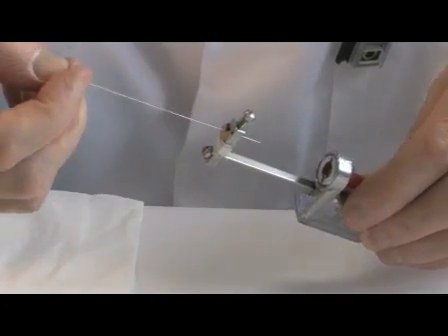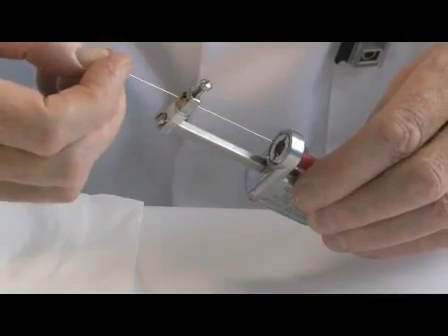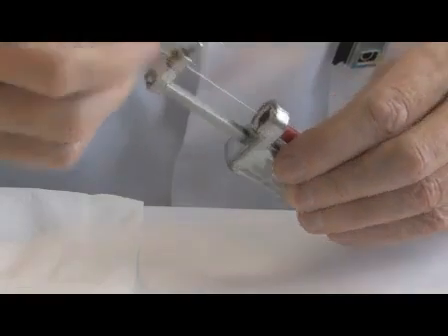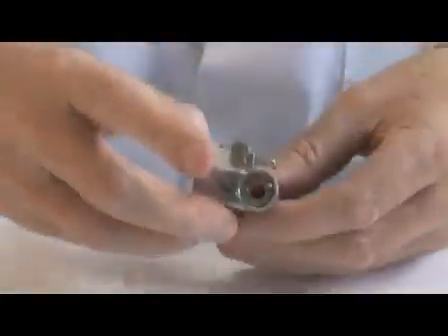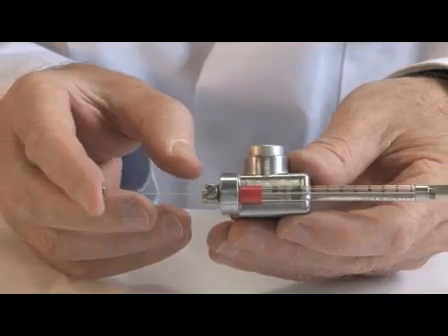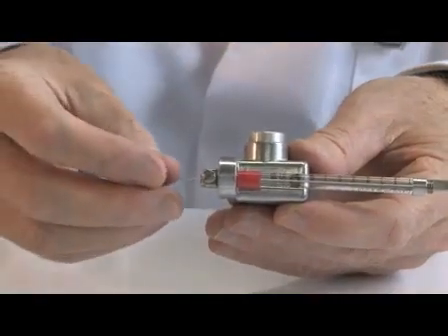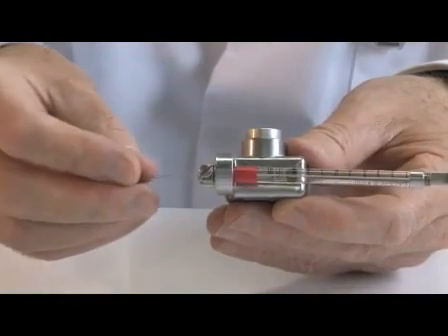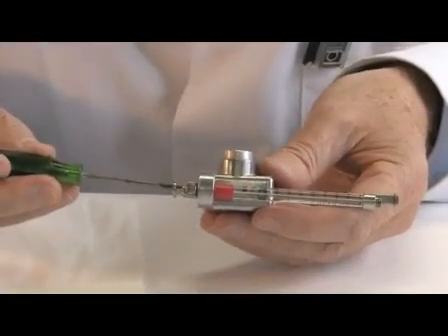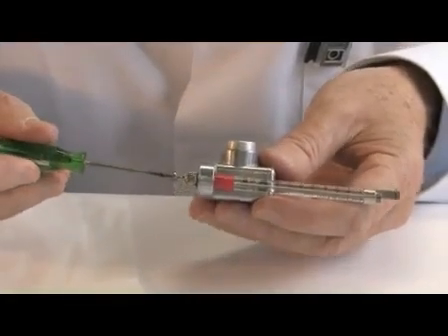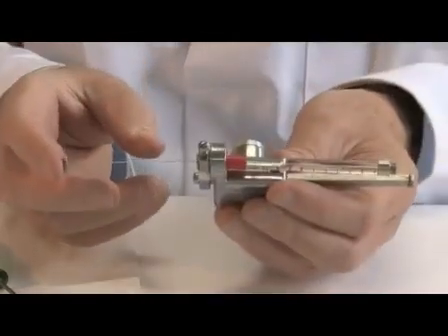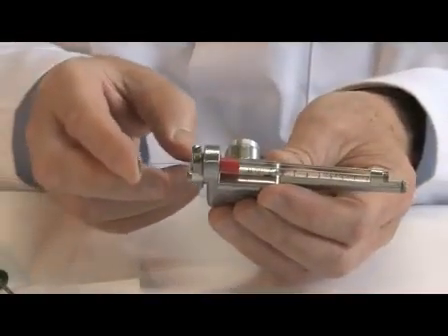Pass the plunger through the gripping ring with the gripper nut unscrewed a few turns and guide the plunger into the open end of the syringe. Depress the ratchet arm fully. Move the plunger into the barrel and check that it travels freely and true in the barrel. If the screw on the guide bar was loosened, retighten it and recheck that the plunger moves freely. The dispensing syringe is now ready for loading.